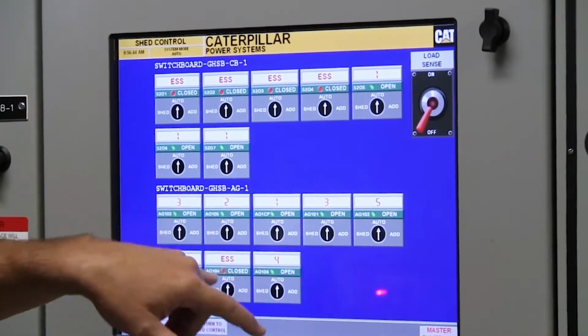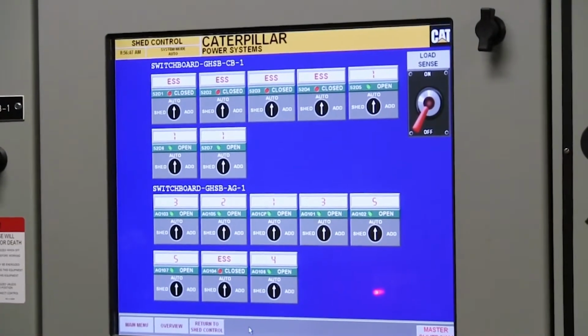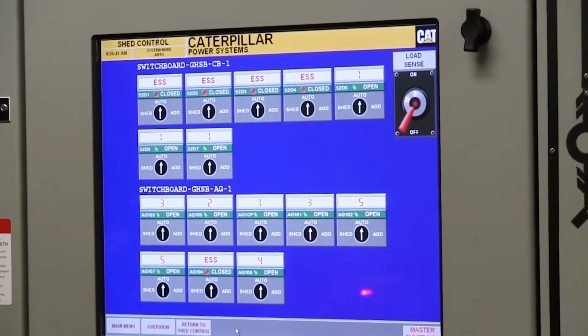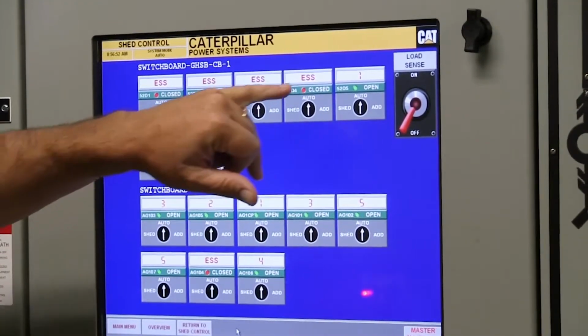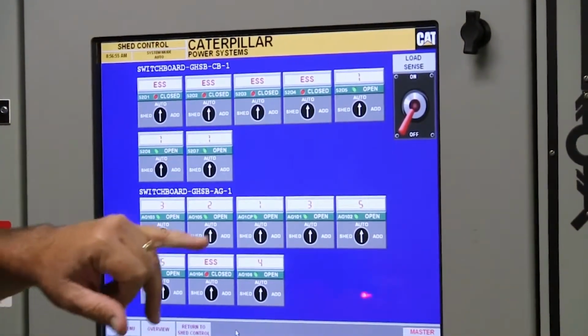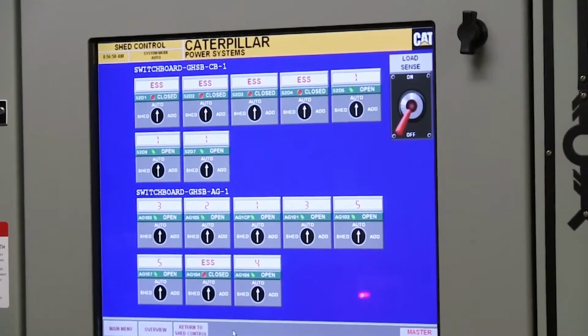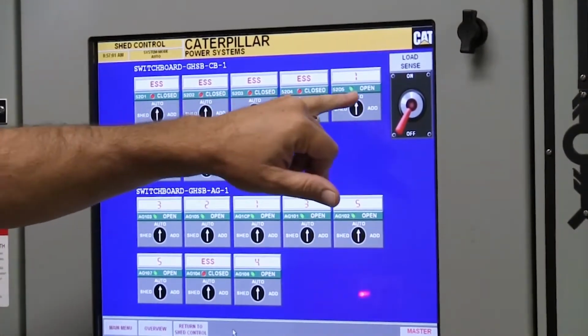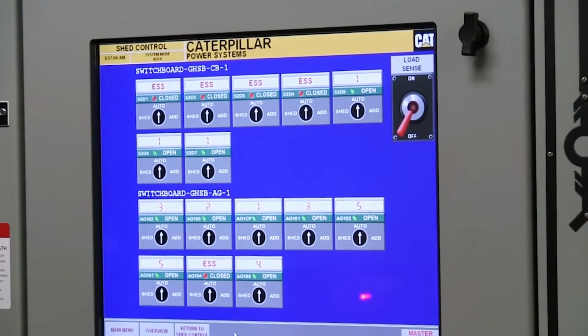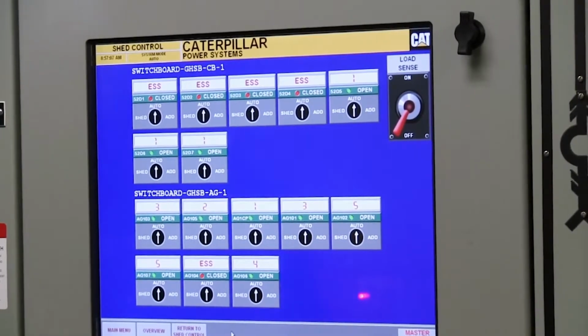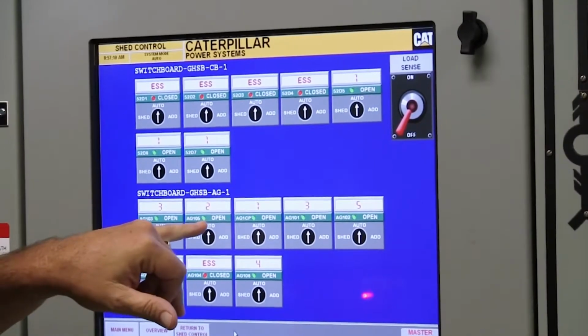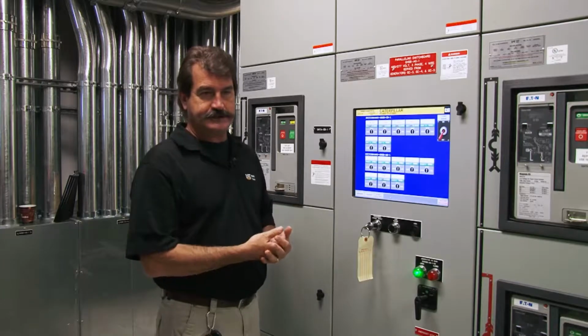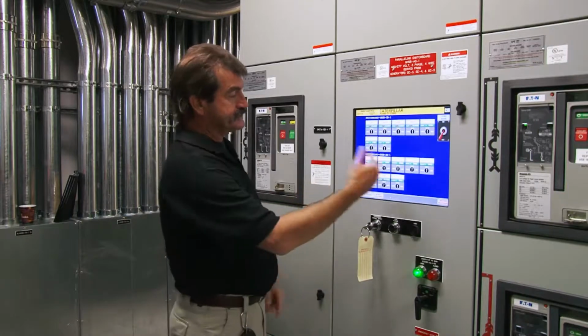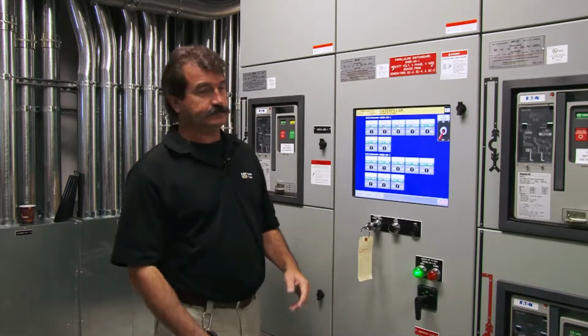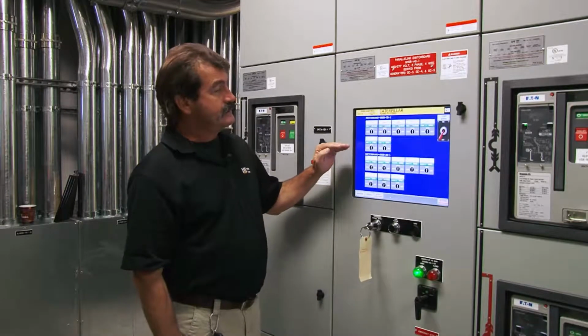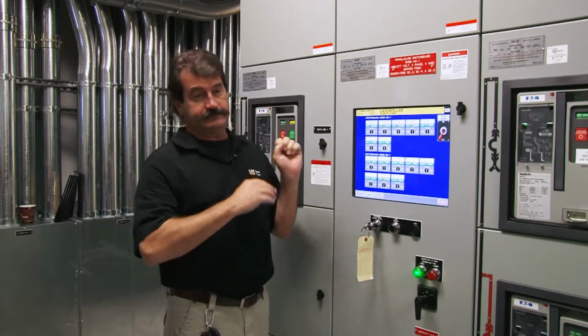1, 2, 3, 4, and 5 correspond to the number of generators that you have on the bus, okay? So if you have 1 generator on the bus, then that circuit breaker will close, all right? So that is priority 1. Anything priority 1 will close as soon as that first generator hits the bus, okay? Likewise with priority 2. That second gen hits, that one closes in. And then we just step on down the line, 3, 4, and 5, okay? And after all those close.